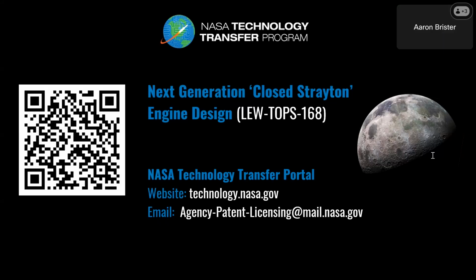You say that it reduces NOx, but how does it do that if it uses a multiple fuel oxidation inlet? Flameless oxidation was accidentally discovered in the late 80s, and it's used today in a lot of industrial applications. Flameless oxidation runs at lower oxygen. Normally when you're burning something, you're at 20% oxygen. With flameless oxidation, you're operating about 6 times lower, so about 3%, at higher temperatures. So you naturally have less oxygen available to form NOx, SOx, and other global warming gases. By using flameless oxidation, you minimize the pollution from your fuels.